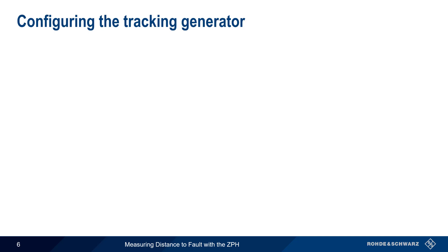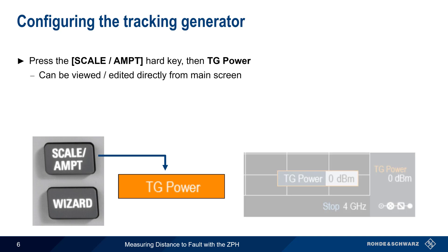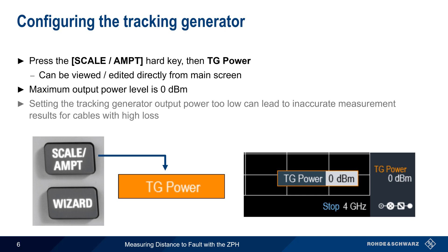The ZPH's internal tracking generator, or signal source, is configured by pressing the Scale Amplitude hard key, and then selecting TG Power from the menu. Note that the tracking generator power can also be viewed and edited directly from the main ZPH screen. The maximum configurable output power is 0 dBm. Care should be taken not to set the tracking generator output power level too low, since this can lead to inaccurate measurement results for cables with high loss.